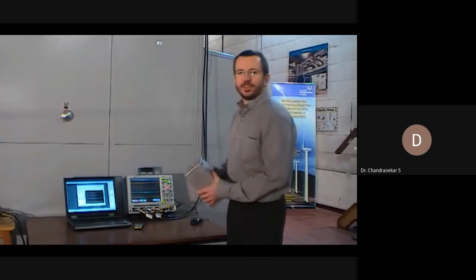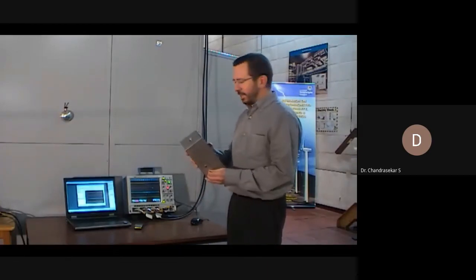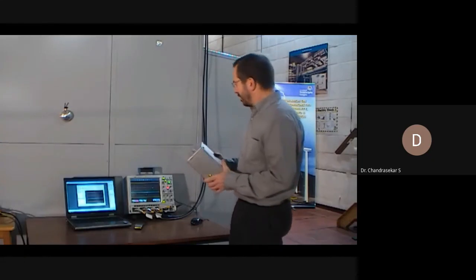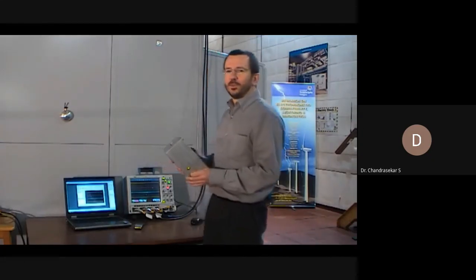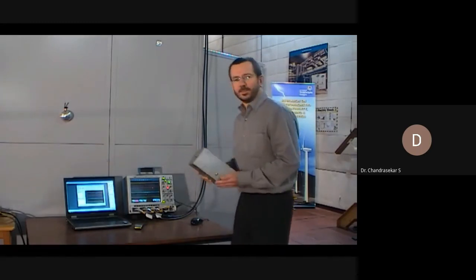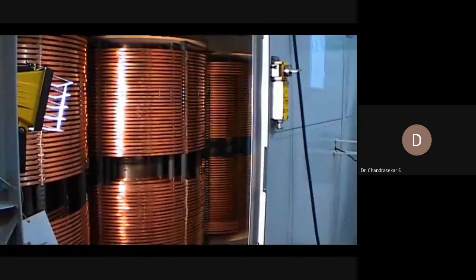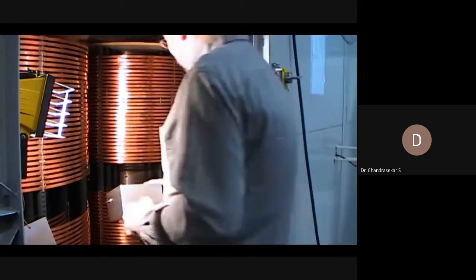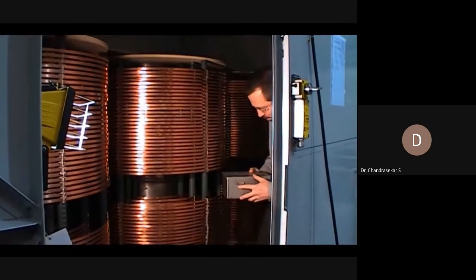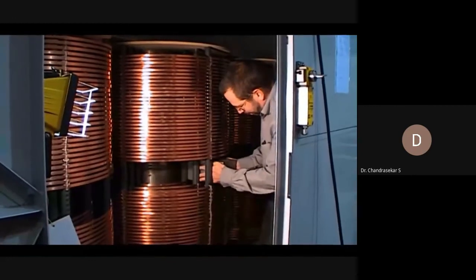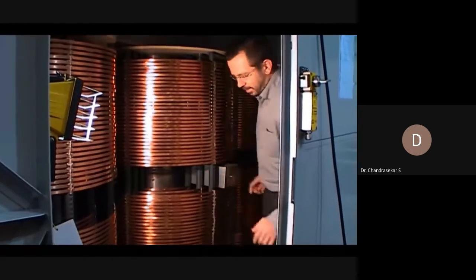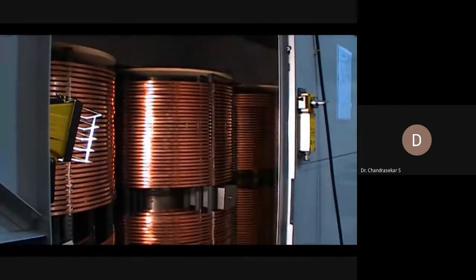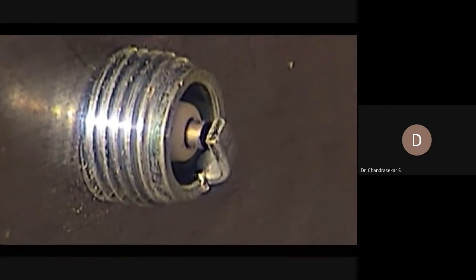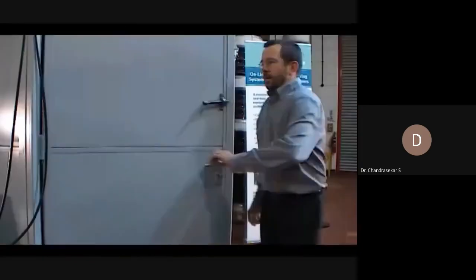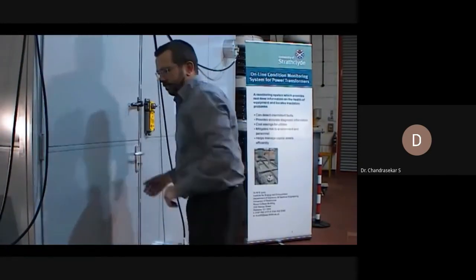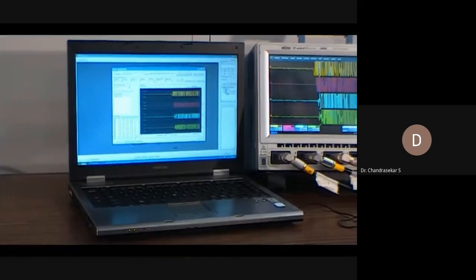To simulate a partial discharge in this tank, we're just using a small spark plug here which will generate a spark every 2 seconds. I'm going to place that in a certain position in the tank, and we'll see how accurately the software can locate it. For the first test, I'm going to put the spark plug here in the center winding, halfway up, just about level with the outer surface of the winding. The data is being logged now.